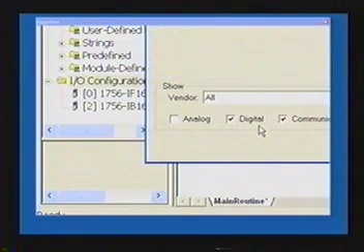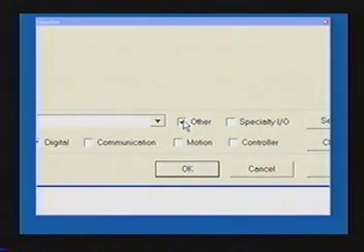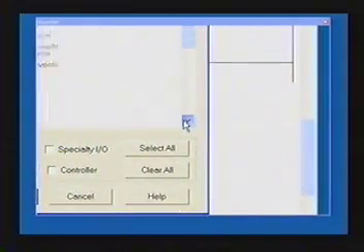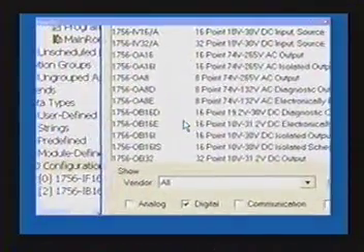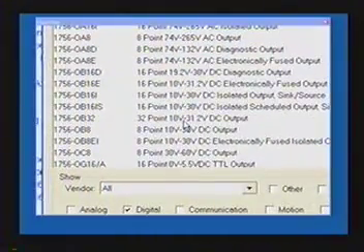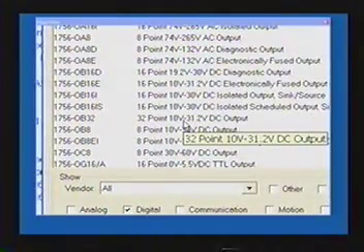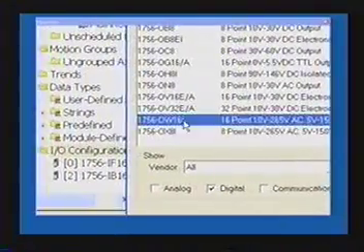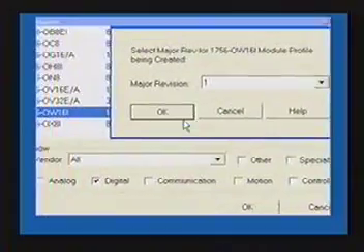And again, the reason I'm going through this again is because this is kind of like your final opportunity to see how an entire process would be looked at from the IS point of view all the way to the PLC input. So let's add an output card, and I really like those OB32s. They're okay as long as you turn on a relay with it, but I really like those OW16s. I like those relay isolated outputs, so we'll say okay to that.